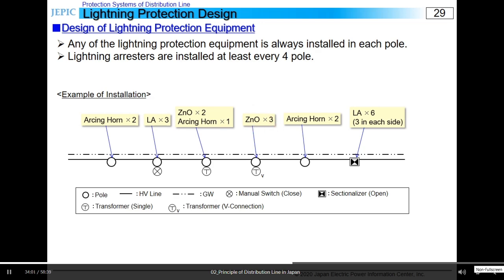On the other hand, when there's only one transformer, two ZNO supporting insulators and one arcing horn are attached to cover all the three phases. If the pole has no equipment, arcing horns are attached to two phases. Lightning protection equipment is installed so that all the poles have either kind of them.